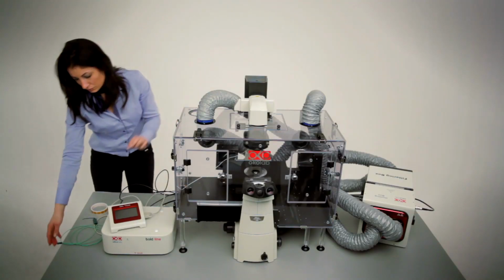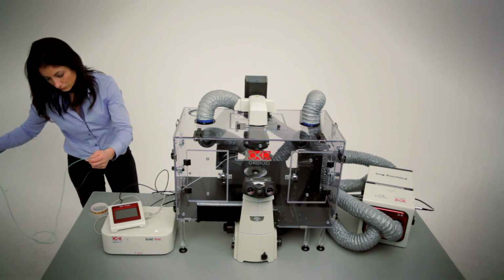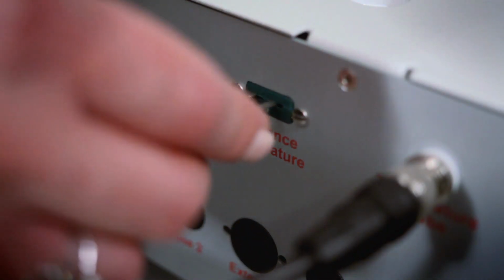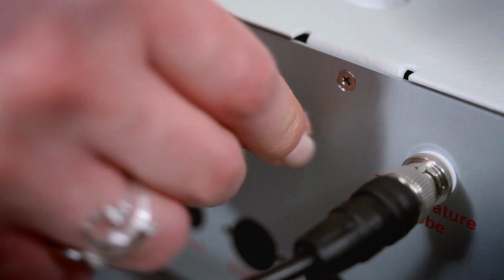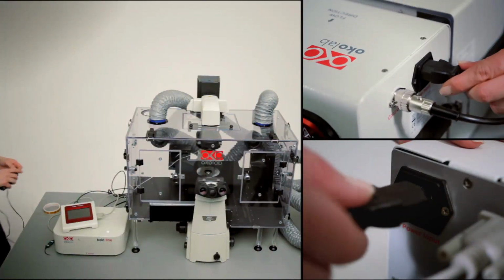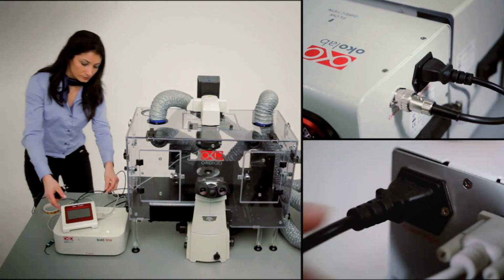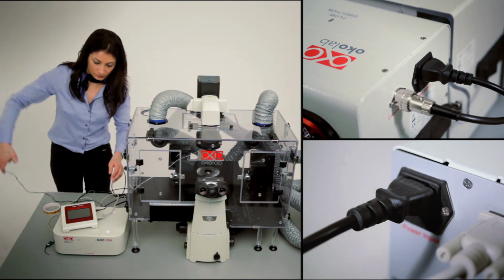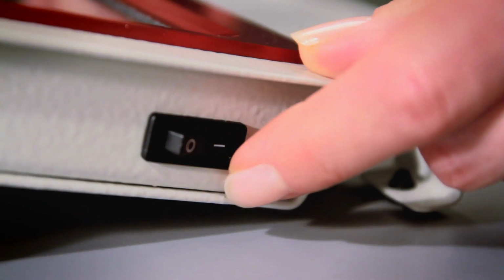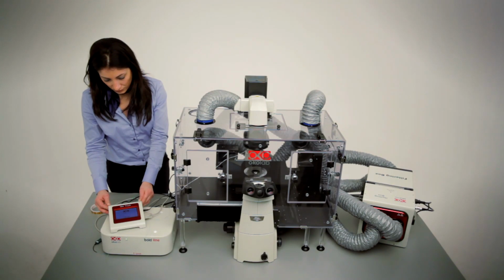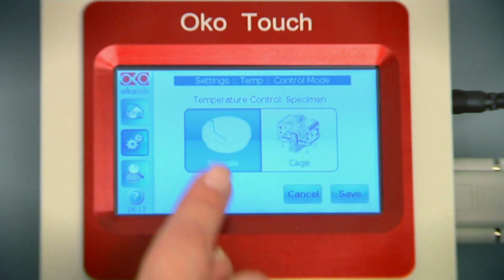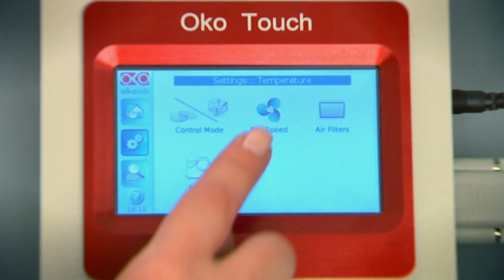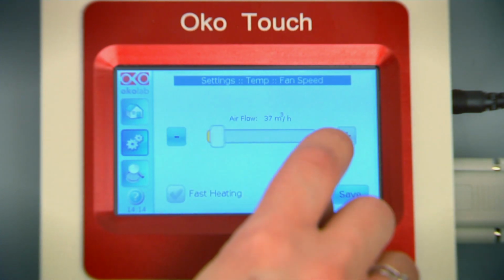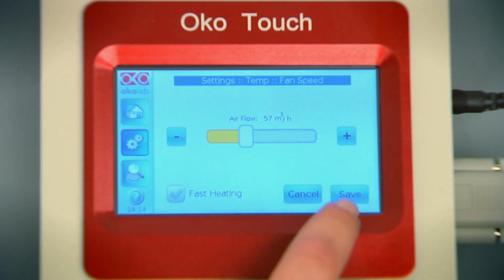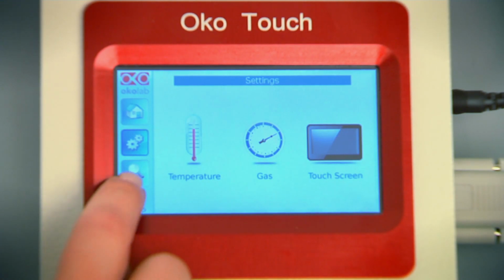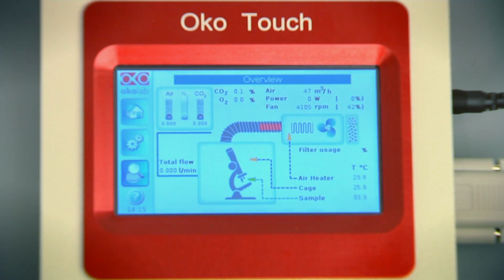Connect the green specimen feedback sensor. The 2 connectors are clearly marked on the rear panel of the temperature controller. Finally, power the temperature controller, the air heater, and the touchpad. The system is switched on and off from the touchpad. The advanced control algorithm keeps sample and enclosure temperature within 0.1 degrees Celsius from set point by stabilizing the temperature and flow rate of the recirculating air in the air heater.